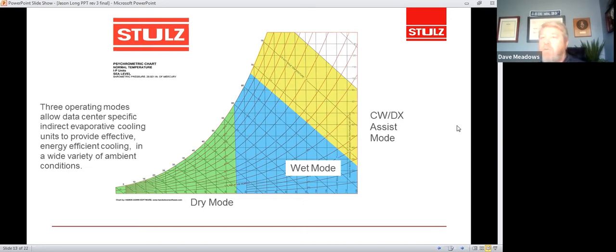So we're able to use evaporative cooling to lower the temperature of the supply air at a very low energy input. Now, as the wet bulb temperature increases, we begin to lose the efficiency of the evaporative cooling, at which point we would bring on a backup DX circuit to provide primarily a trim cooling effect. In other words, we don't have to remove the entire heat load with the compressors. We just have to knock it down that last couple of degrees to get back to set point.